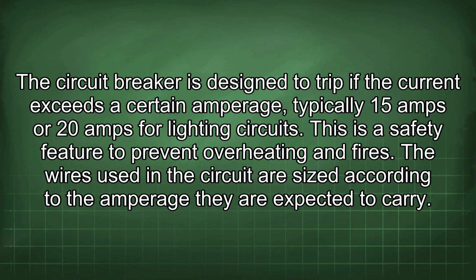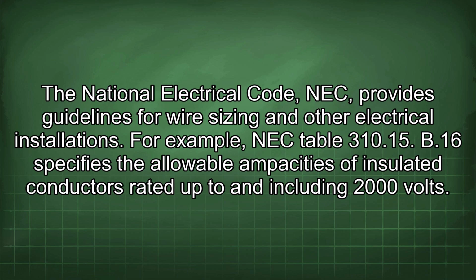The wires used in a circuit are sized according to the amperage they are expected to carry. The National Electrical Code, NEC, provides guidelines for wire sizing and other electrical installations. For example, NEC Table 310.15(B)(16) specifies the allowable ampacities of insulated conductors rated up to and including 2000 volts.